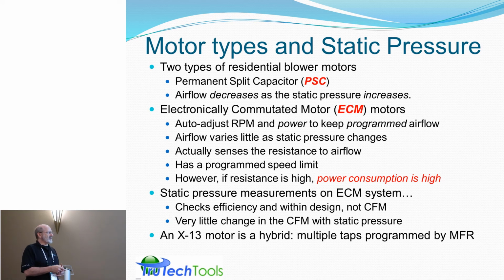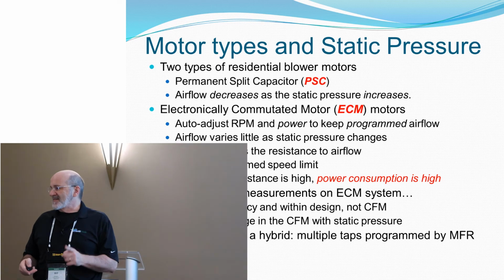And we'll show the power consumption, although somebody pointed out, I think he's still in the room, that I've got to look at volts or watts and amps. Yes. I didn't take care of that in this, wasn't that quick with it. But the static pressure in an ECM system really doesn't tell you a lot about airflow because it's a programmed airflow. And actually a manufacturer did produce an airflow chart.